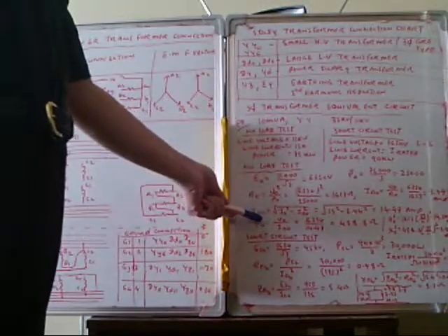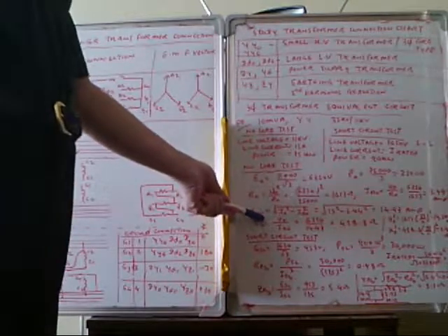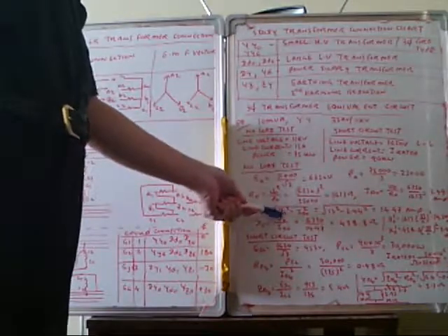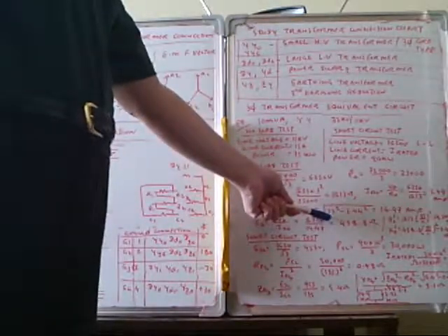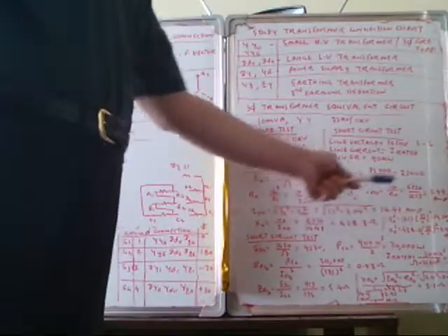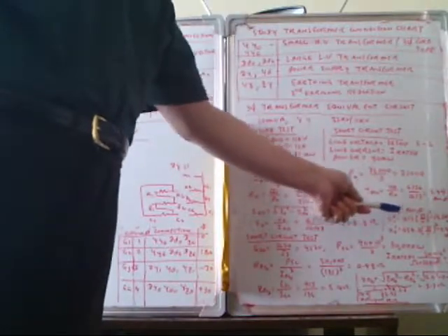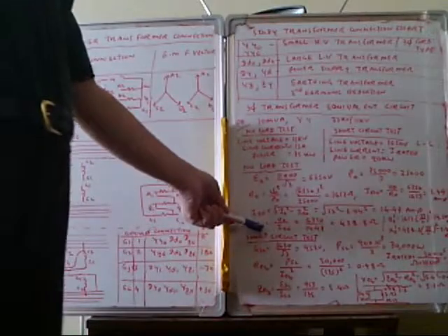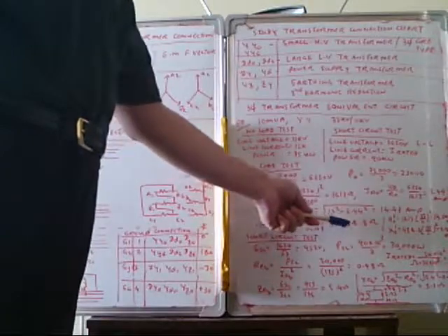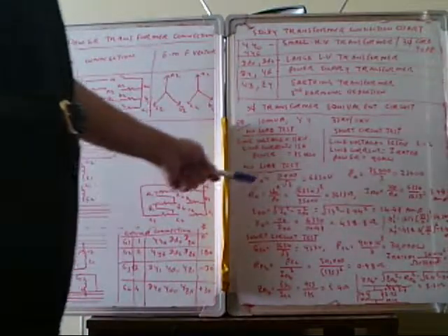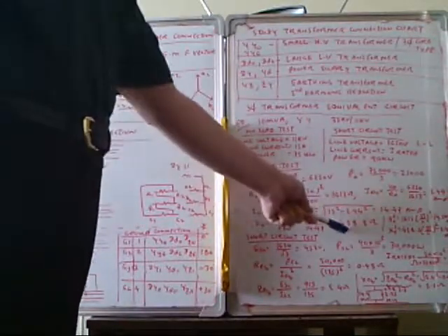The current flowing through the magnetizing component, the formula is square root of I0 squared minus IR0 squared. So I0 is 15 ampere squared, and IR0 is 3.94. So you got 14.47. The magnetizing reactance is V0 by IM0. So V0 is 6350 and IM0 is 14.47, so 438.8. So these two values are what we get at the secondary side.